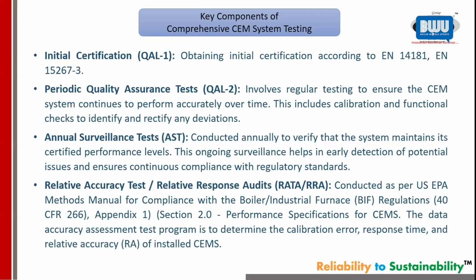So we'll discuss the periodic quality assurance test. After your QAL-1 equipment is purchased and installed at your place, quality assurance testing has to be conducted every 5 years to do calibration and functional checks, identifying and rectifying any deviations. Any measuring equipment tends to drift, so to manage that drift, you need testing.